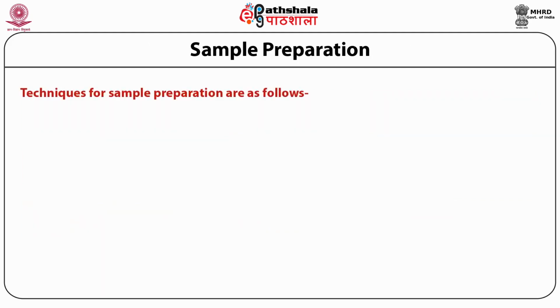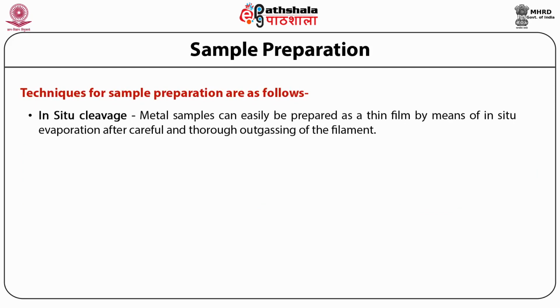There are several methods for sample preparation. First one is in situ cleavage. In this technique, it is a very good method for exposing a new fresh clean surface from single crystals of most semiconductors, insulators and layered compound samples. Most metal samples can easily be prepared as a thin film by means of in situ evaporation after careful and thorough outgassing of the filament.